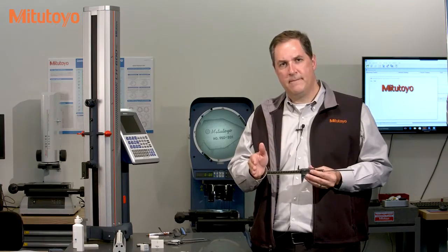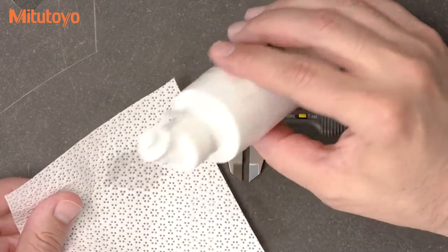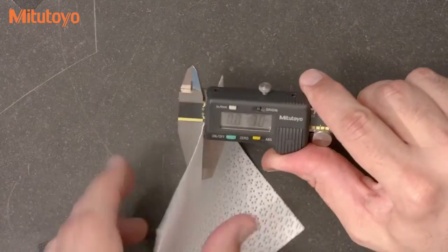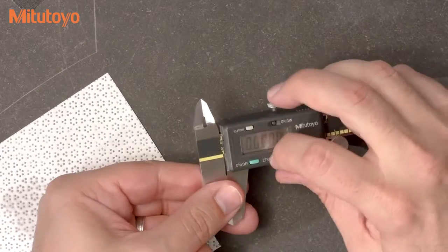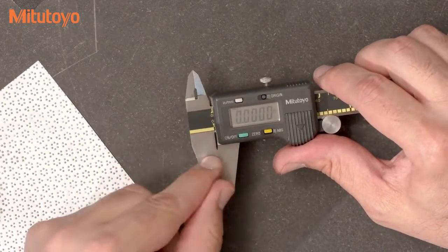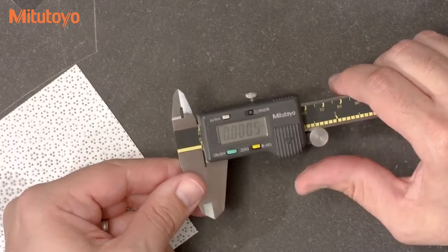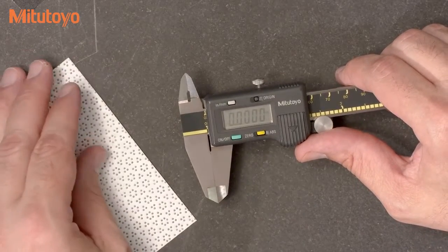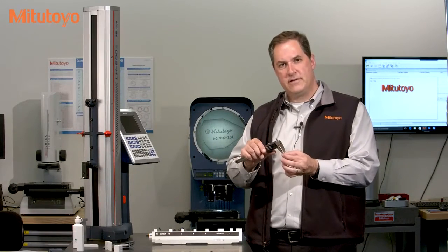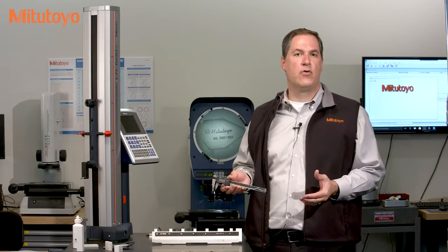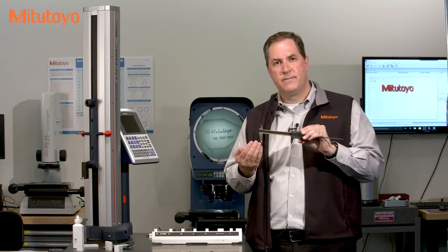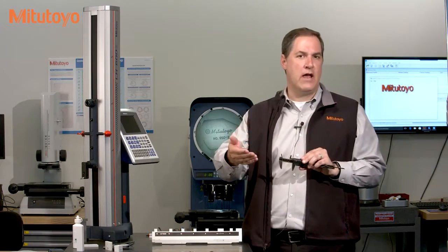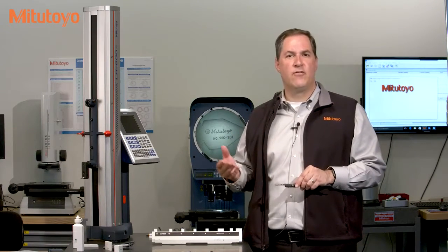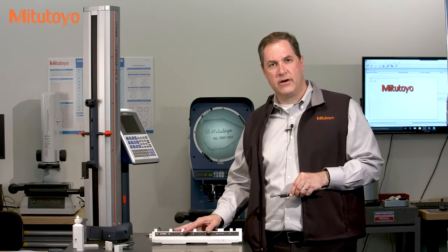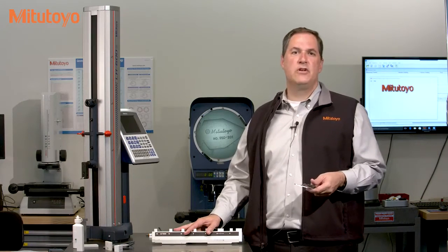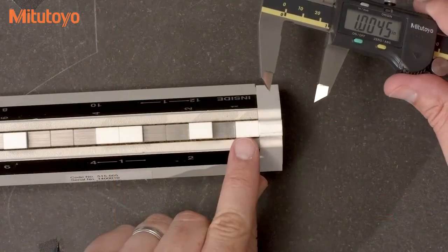Now let's look at this method more carefully. First, we will clean all the measuring faces, and then bring the outside measuring faces together to set our 0. We will double check our 0. But when we're done with that, we won't change it again during the calibration. The first test is with the outside measuring faces. For a 6-inch caliper, the ASME standard requires a minimum of 3 points across the measuring range. The minimum then increases for larger calipers. We will take 4, as that is convenient for the reference standard that we're using, which is this Mitutoyo caliper checker. This is a nice standard for calibrating calipers, but you could use any grade or material gauge block as well. We'll start at 1 inch.